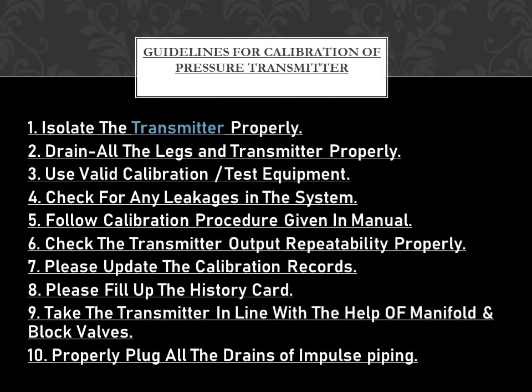Guidelines for calibration of pressure transmitter. First of all, isolate the transmitter properly. Drain all the legs and transmitter properly. Use valid calibration test equipment. Check for any leakages in the system. Follow the calibration procedure kept in the manual. Check the transmitter output repeatedly and properly.